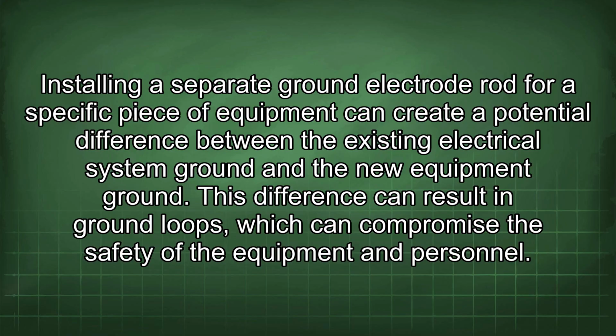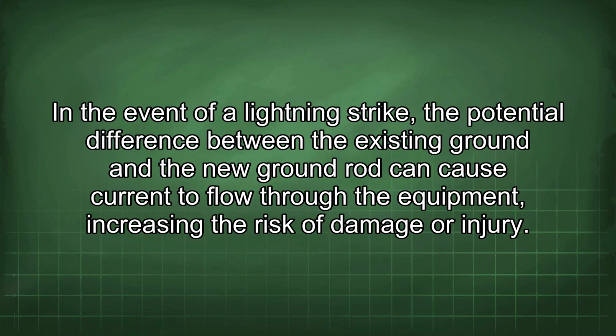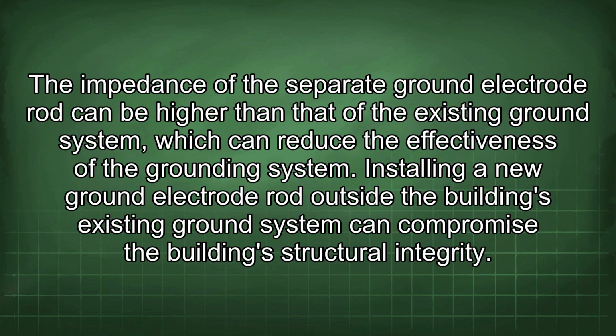This difference can result in ground loops, which can compromise the safety of the equipment and personnel. In the event of a lightning strike, the potential difference between the existing ground and the new ground rod can cause current to flow through the equipment, increasing the risk of damage or injury. The impedance of the separate ground electrode rod can be higher than that of the existing ground system, which can reduce the effectiveness of the grounding system.